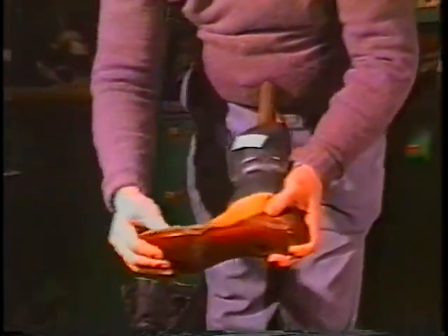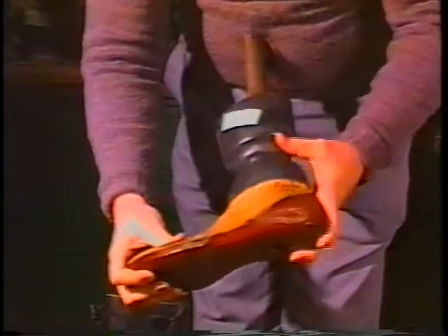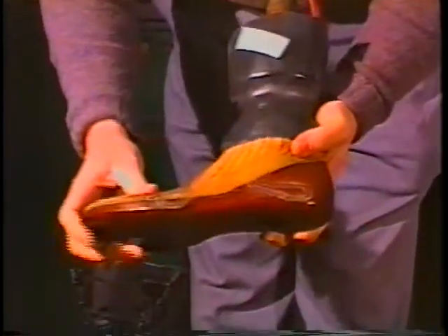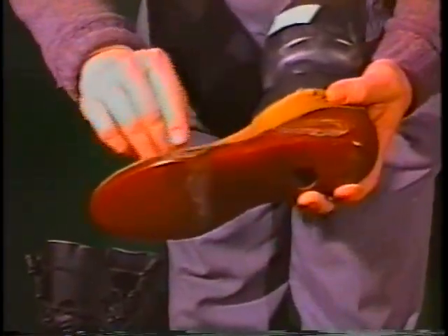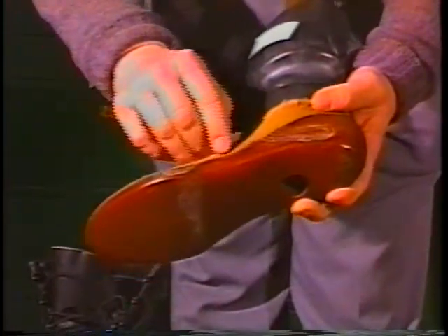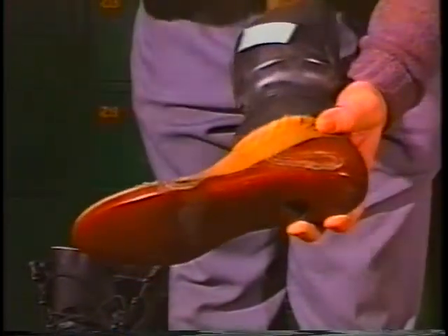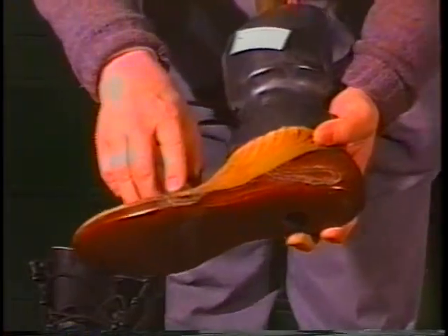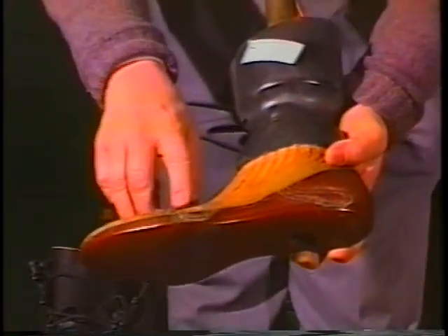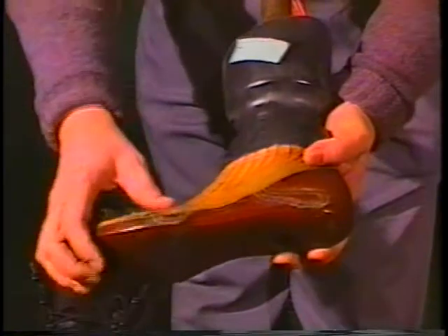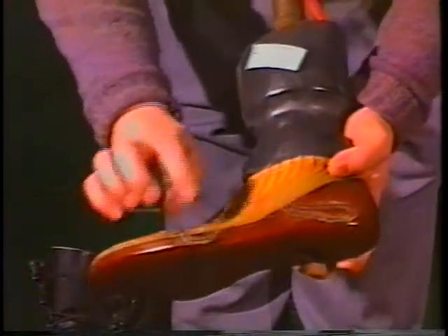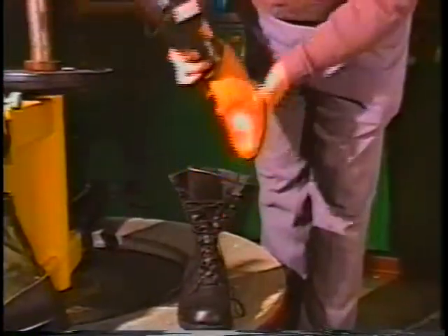This is actually a prosthetic foot that would be used for an amputee, modified to include electrical wires which provide circuits that will be shorted if the water, which has some saline added to it, gets through the boot as it walks. So this boot - I happen to have a right foot and a left boot, or vice versa - this will go into the boot, and the boot will then be placed on the machine.